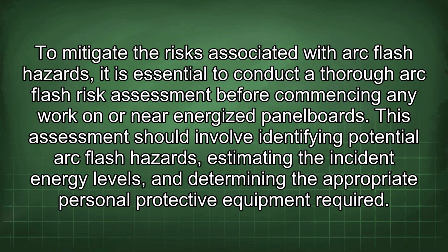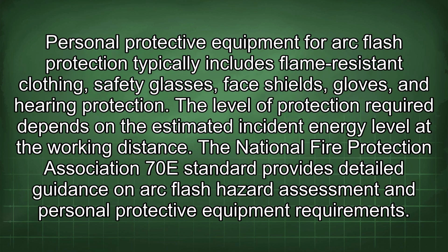This assessment should involve identifying potential arc flash hazards, estimating the incident energy levels, and determining the appropriate personal protective equipment required. Personal protective equipment for arc flash protection typically includes flame-resistant clothing, safety glasses, face shields, gloves, and hearing protection. The level of protection required depends on the estimated incident energy level at the working distance. The National Fire Protection Association 70E standard provides detailed guidance on arc flash hazard assessment and personal protective equipment requirements.